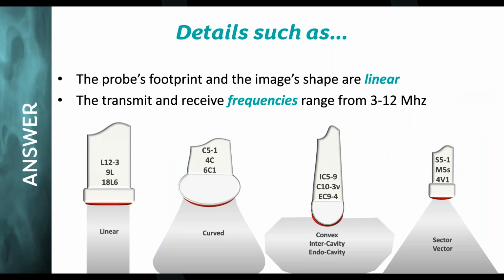Yeah. So usually, and there are some exceptions, the letters denote the type of probe and the image format, and the numbers typically denote the frequency range. I know the C is for curved, and those are mostly for OB. They can be, but then you see over here there's a C10-3, IC, EC. IC stands for intercavity, so that is an endovaginal probe. The C10 is also an endovaginal probe, as is the EC9-4. There are also intercavity probes, not exclusive to women. Us men can be on the receiving end as well. There are prostate probes for urology, where they're utilized to diagnose prostate cancer.